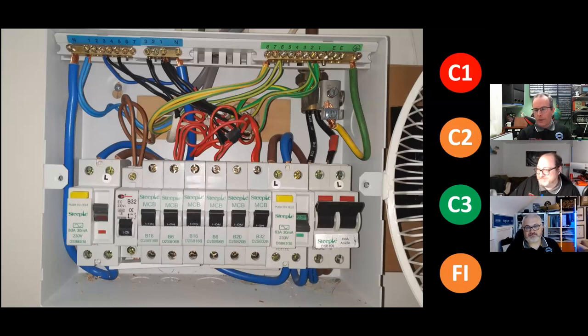The pyro is not attached to the consumer unit body. They've just cut a massive hole out of the top. It's just floating in. They passed it through, floating, and then they've attached that clamp. They have, because the body of the pyro is bigger, isn't it? And the bush. I would have probably gone to actually re-gland that and have a dedicated CPC into a metal enclosure. Yeah, that should have been glanded correctly into a metal enclosure with a dedicated CPC.